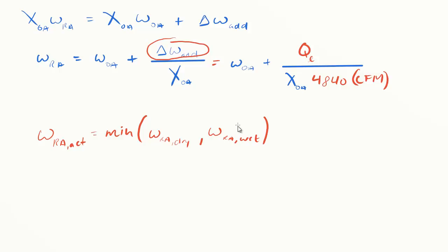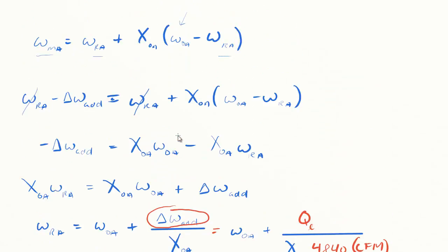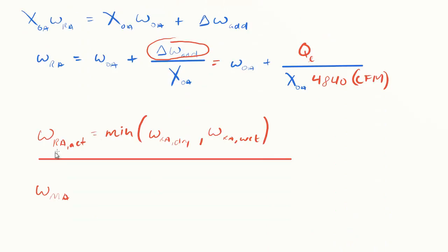The wet case sets your upper bound. At no point can anything be more humid than that, so if your calculation is telling you that, then it must not be correct and the other one is truly correct. This is our final formulation. If you wanted omega mixed air, you can simply use that mixing formula we had. This is always valid in both cases. We have both our return air actual and our mixed air for the single duct case.